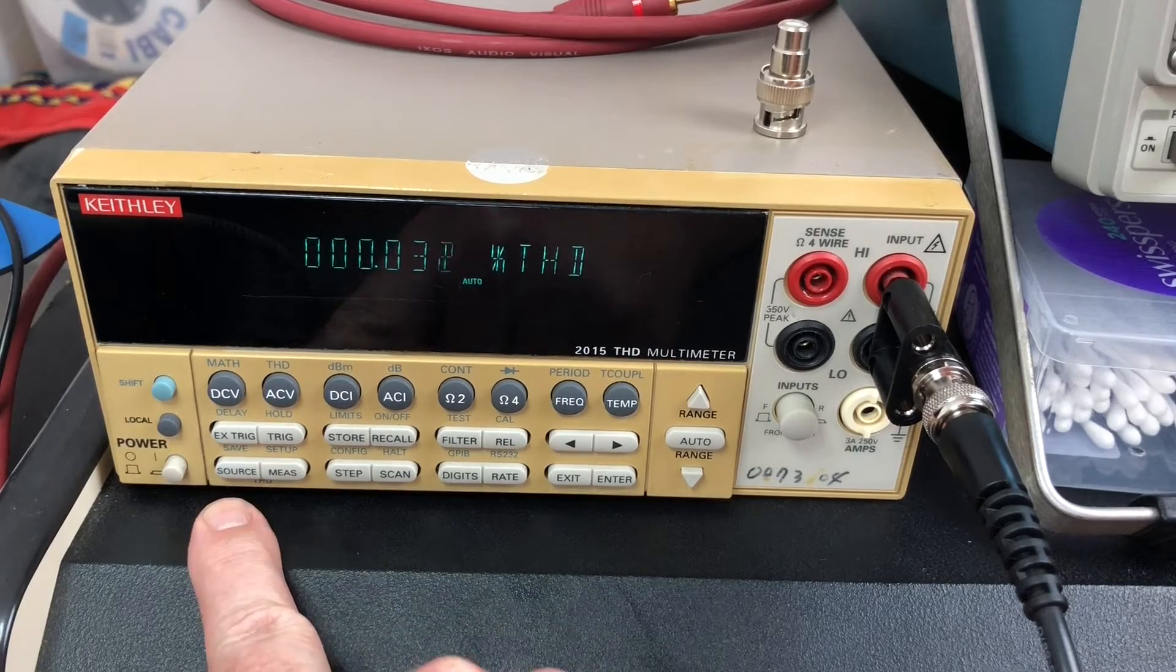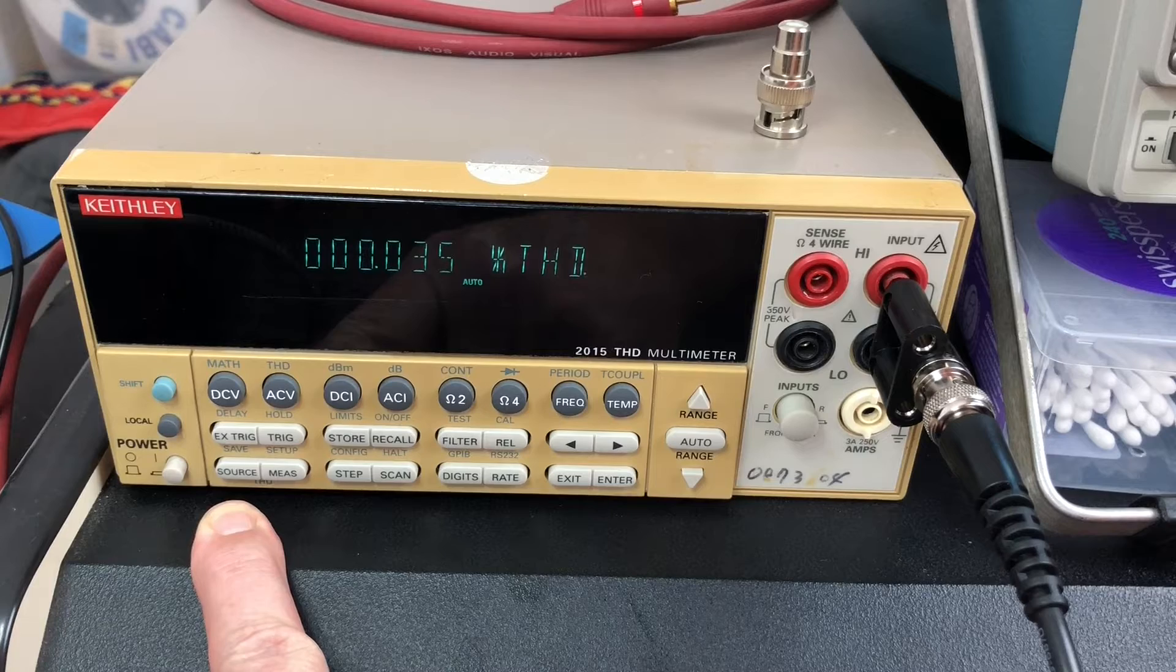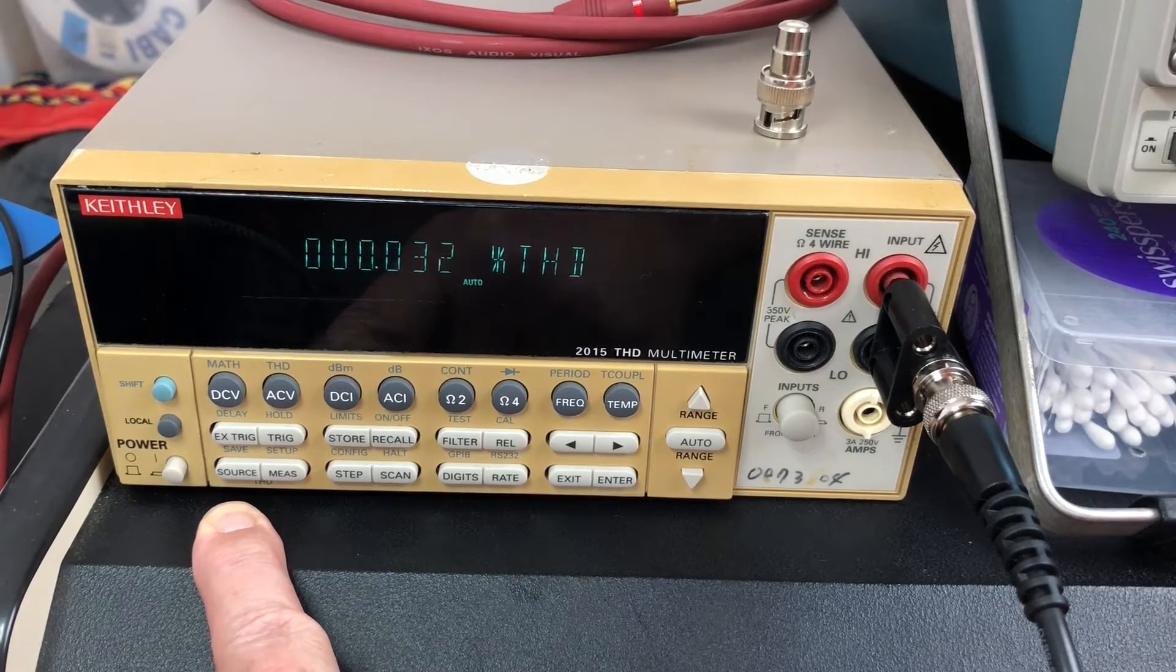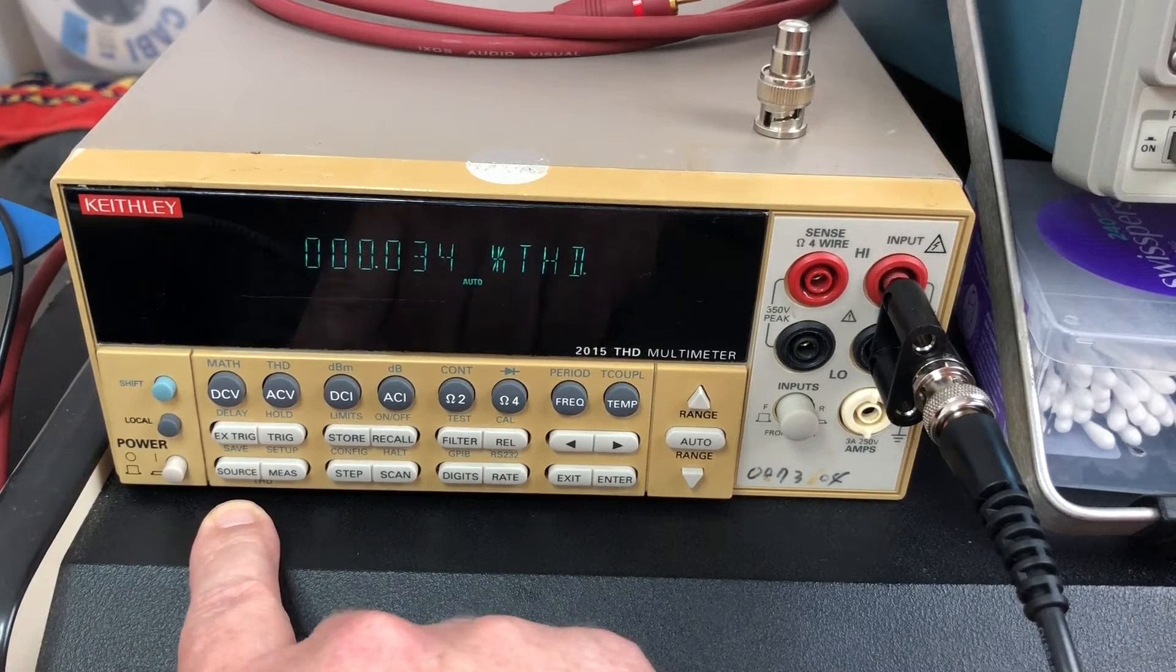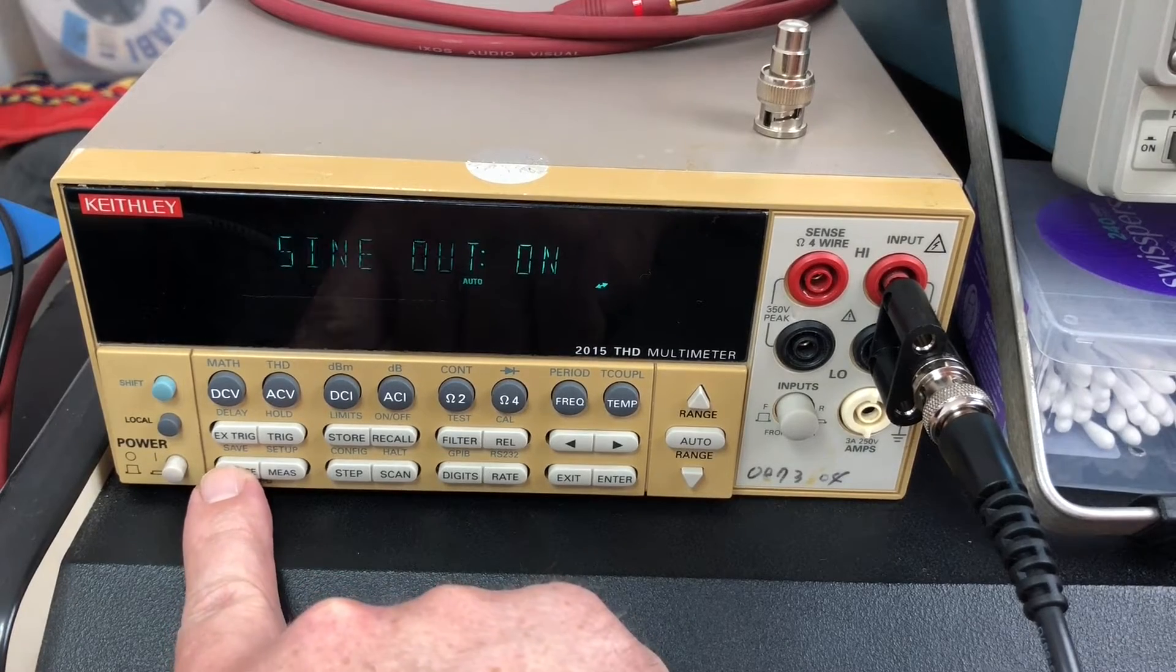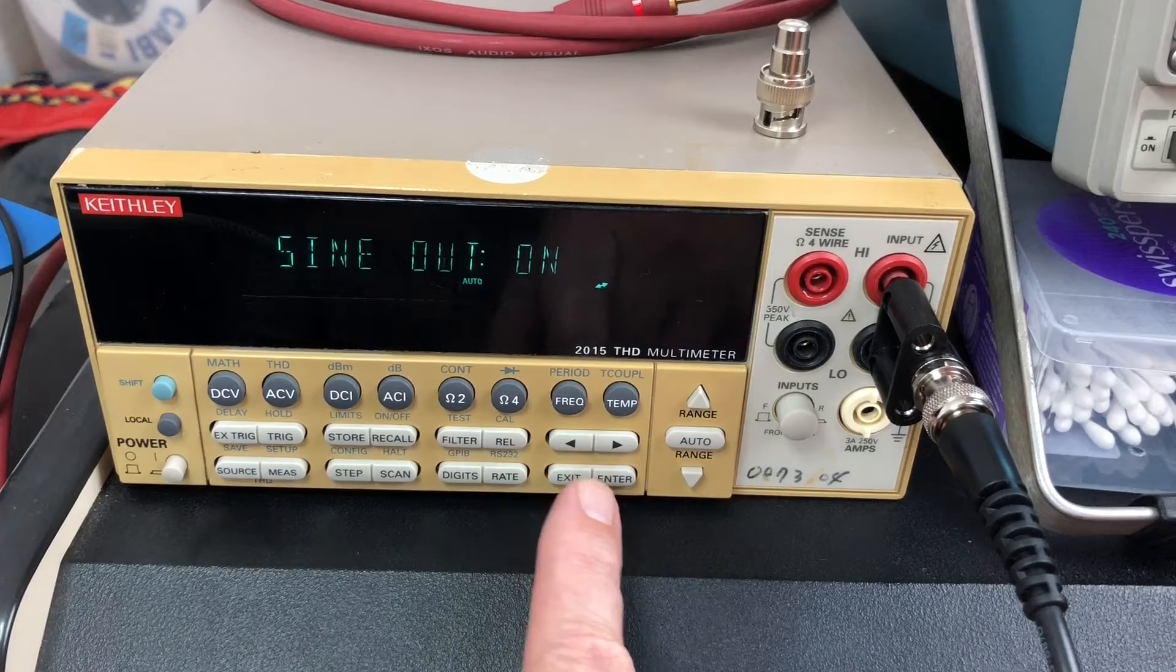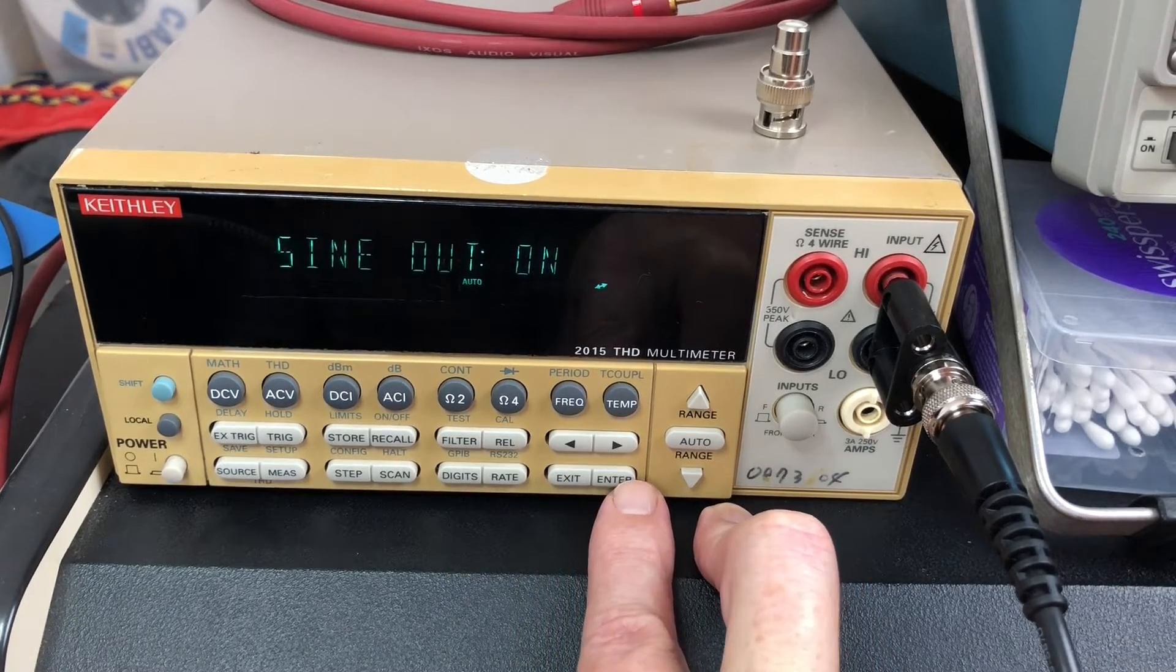The source is a sine wave generator built into this thing. You could use an external sine wave generator, but you need a very pure signal, so this has one built in. The source button allows you to configure that - sine out, whether the signal generator is on or off, then you set your frequency.